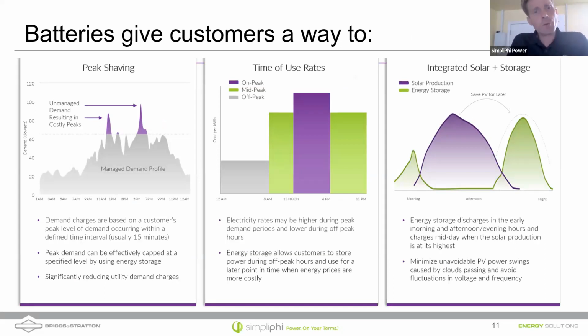Well, let's have a look at the things that we can do if we have batteries on our solar system. One of the things we can do with batteries is we can shave off peak rates. So there are some ways that electricity companies will charge extra fees, and let's suppose that you're on a plan that includes peak use rates. So this is a peak demand. So if you're using greater than a certain number, and on the left side of your screen, you can see that I'm showing that there's maybe a peak higher rate charge if you go over about 60 kilowatts, right? So what batteries can do is allow us to produce some of that energy. We'll use some CTs to monitor how much power we're drawing from the grid and produce any excess that we need to stay out of this peak demand region by discharging the batteries and providing that power when that consumption starts to get near the peak rate.